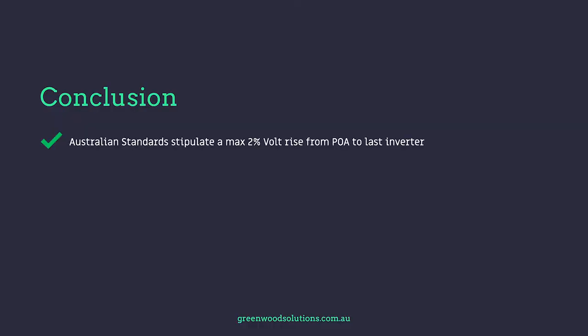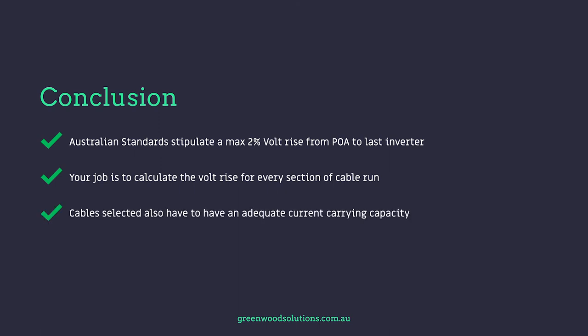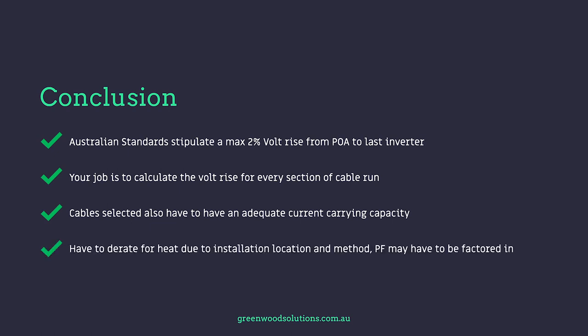Conclusion: Australian standards stipulate a maximum 2% volt rise from point of attachment or point of supply to last inverter. Your job is to calculate the volt rise for every section of cable. Cables selected also have to have adequate current carrying capacity, must be derated for heat due to installation location and method, and power factor may have to be factored in.